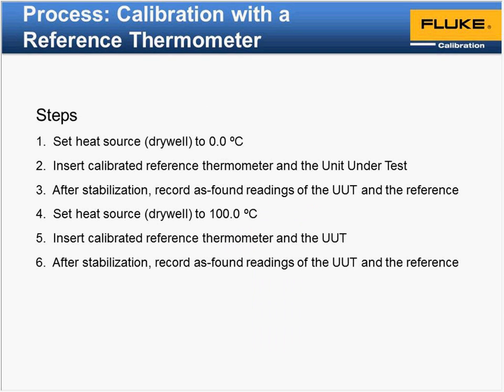The steps that we do are very similar. We're going to set the heat source down, have the units in the chamber or well, and record as-found data, run it back up to 100, get that as-found data, go down to 0, make any adjustments that we need, and then run it up to the temperature, making that adjustment at the high end. Then the slope applies. In some experiences you think everything should be linear, but sometimes you have to give up a little on your top or bottom end to pull in the opposite end. It depends on the range or the accuracy that you're looking for.